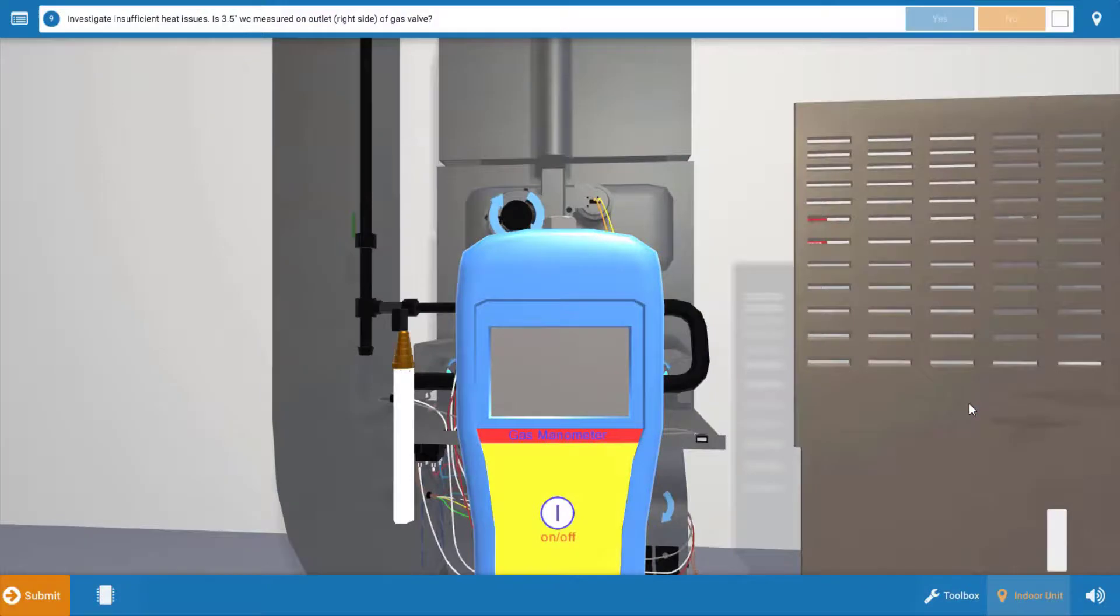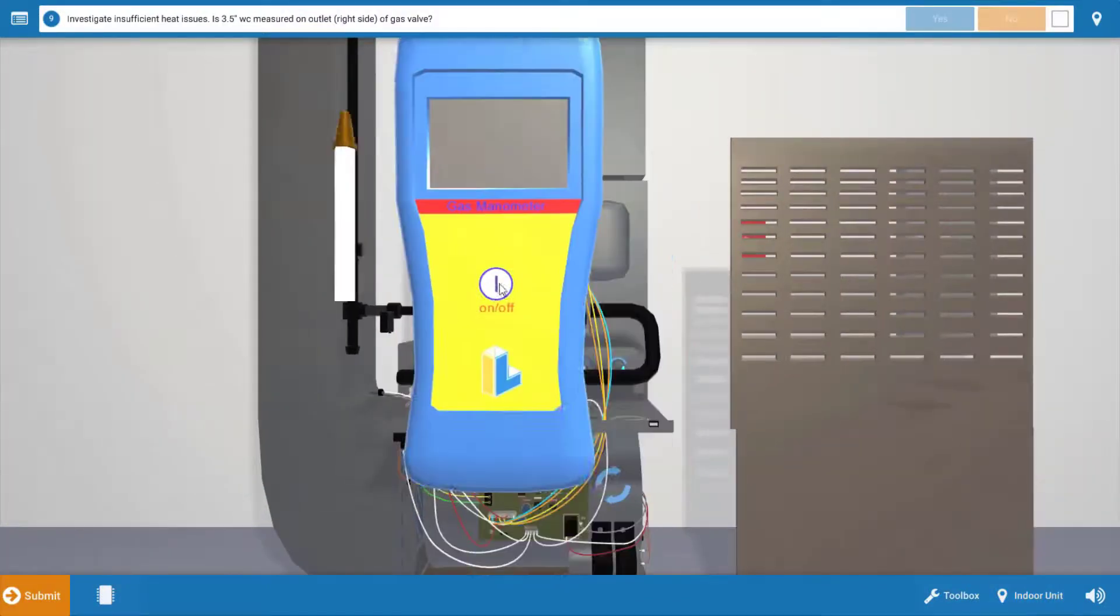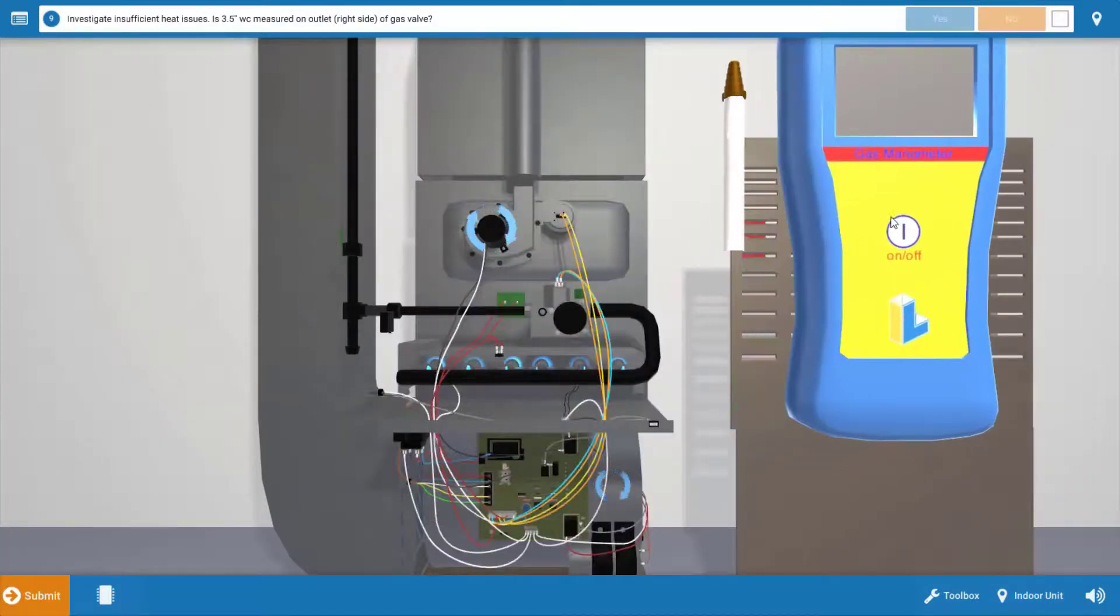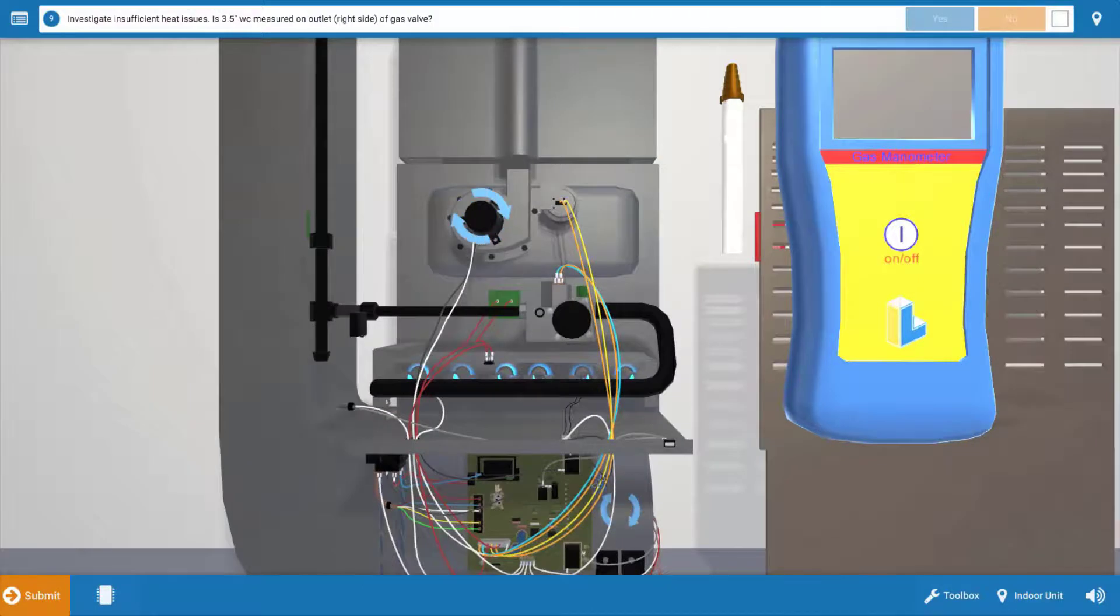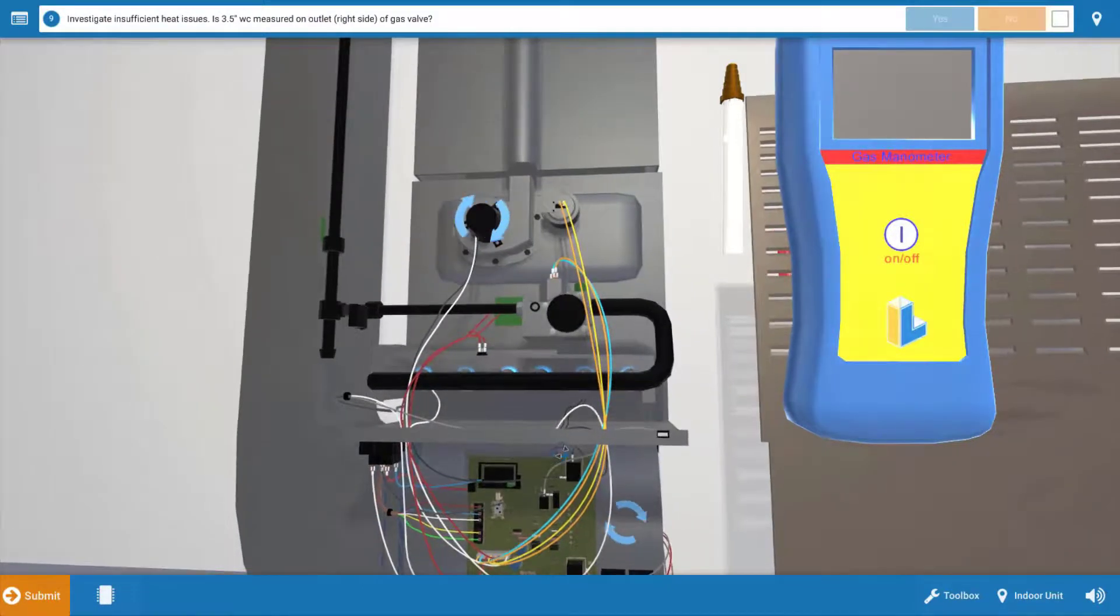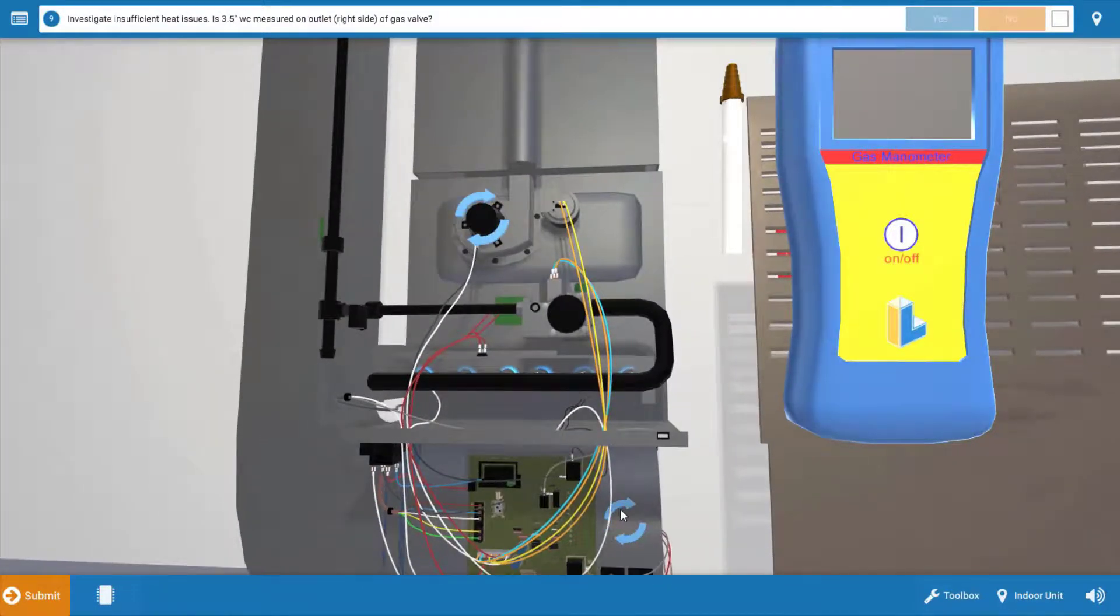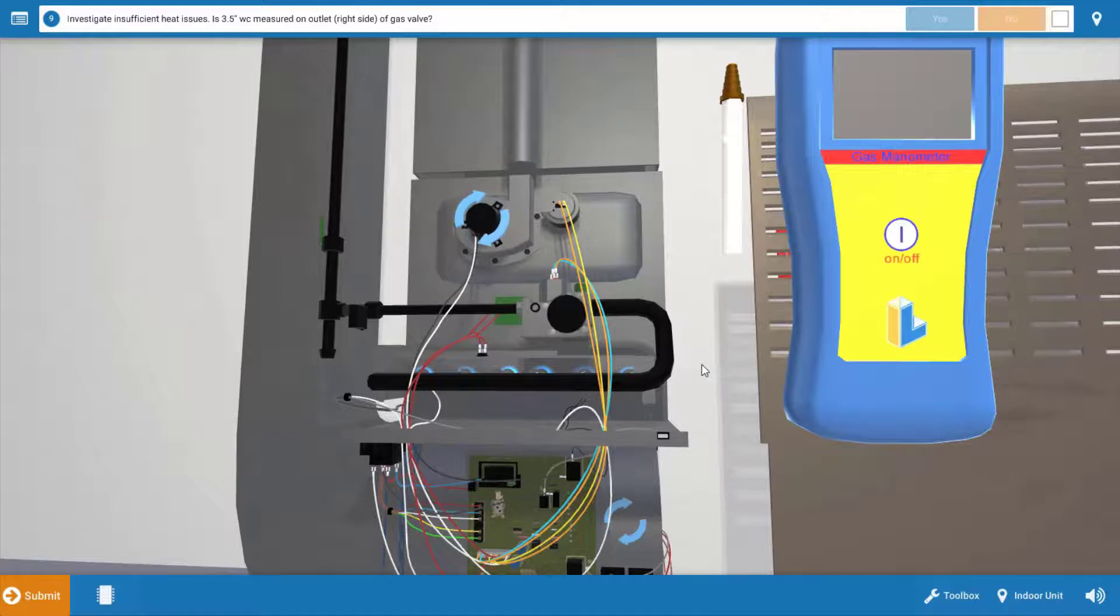If you look on the menu here, you'll be able to locate the indoor fan motor. Just click on the indoor unit. We're going to slide the manometer out of the way, and if we look down here at the bottom, we can zoom in a little bit. We can see that yes, the indoor fan motor is running. So electrically, the entire system is OK.